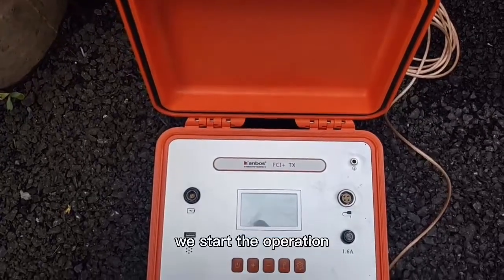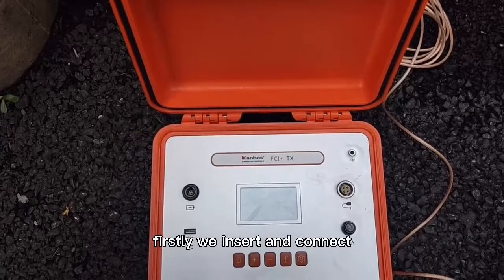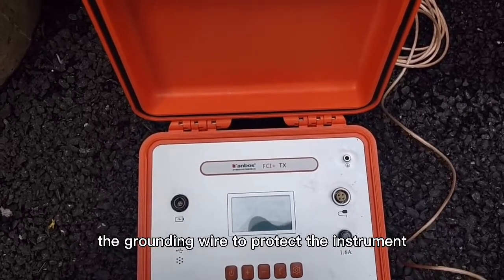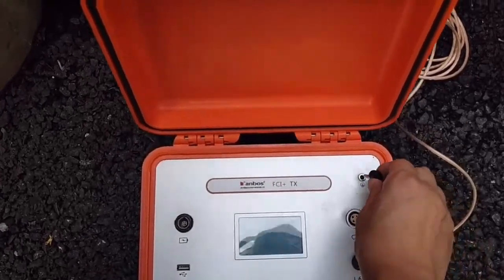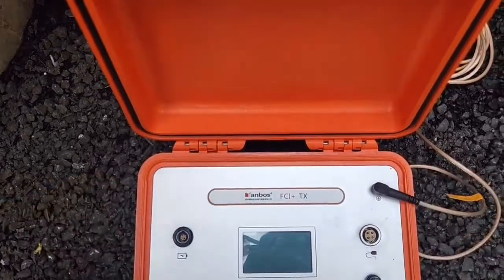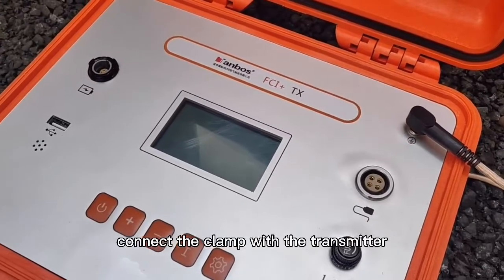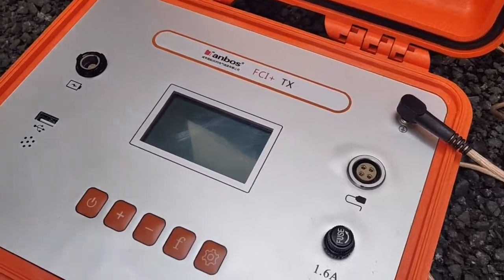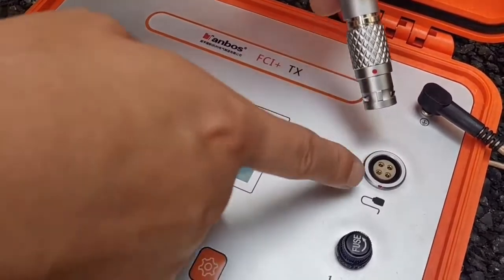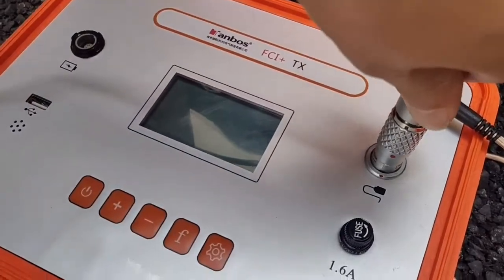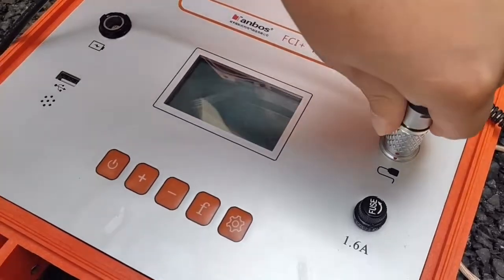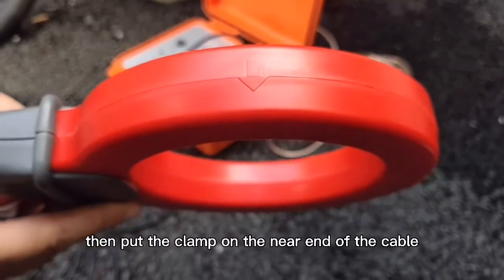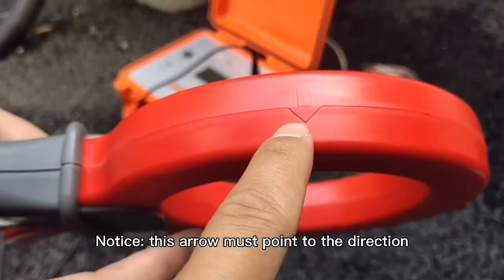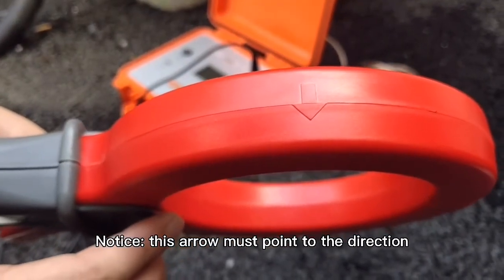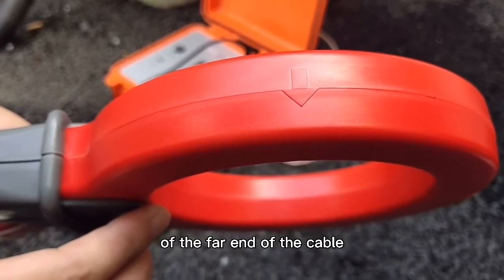Okay, we start the operation. Firstly, we insert and connect the grounding wire to protect the instrument. Connect the clamp with the transmitter. Then put the clamp on the near end of the cable. Notice this arrow must point to the direction of the far end for the cable.